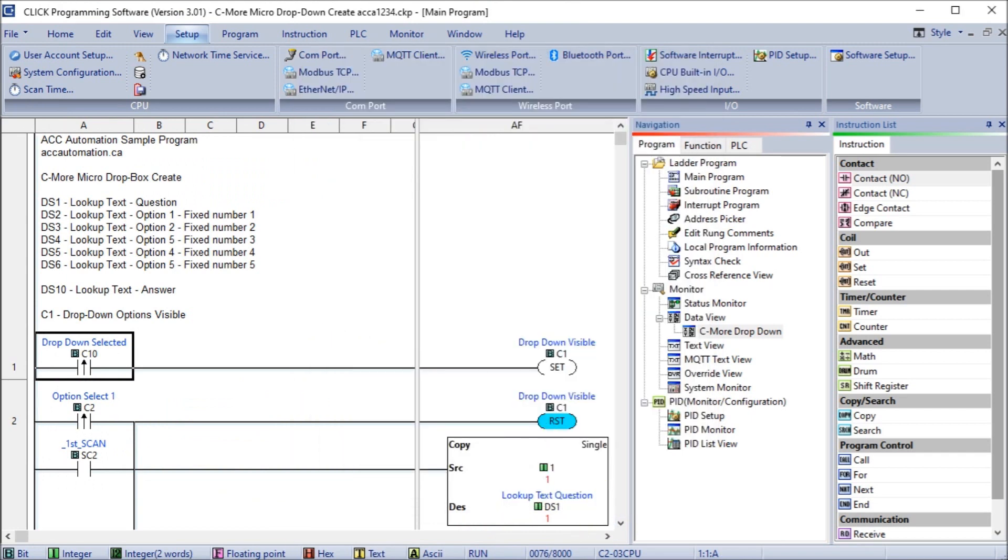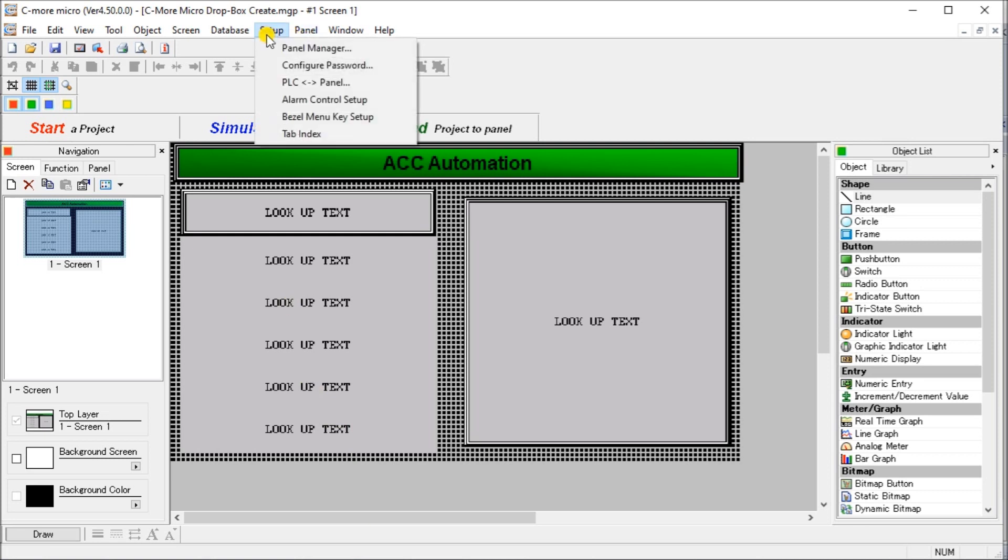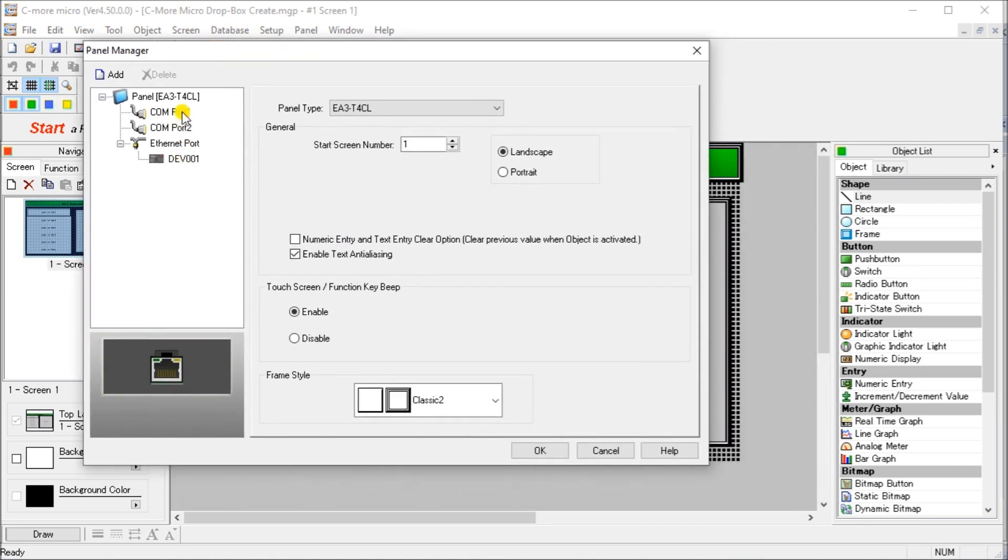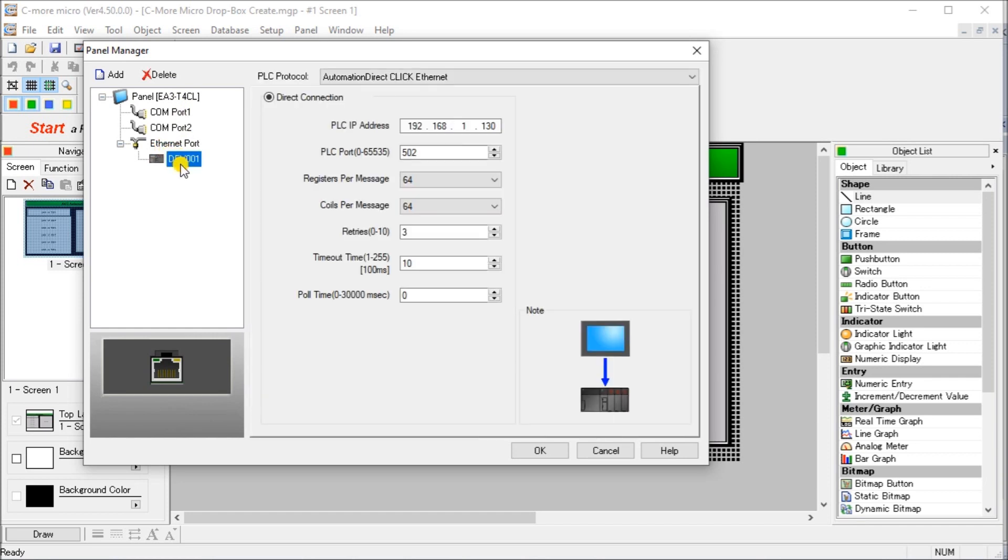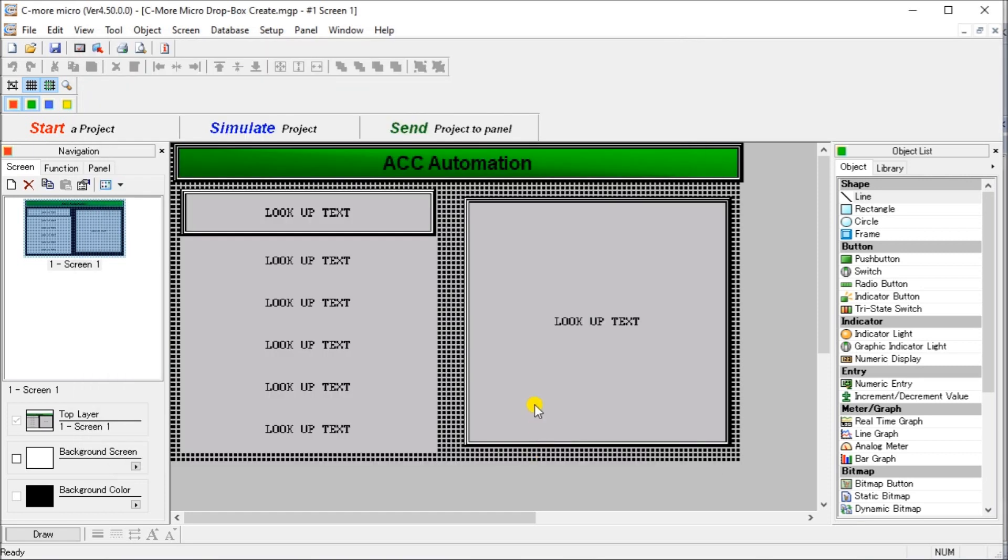So once we have our port set up, now let's go back to our C-more micro programming software and we can go to setup. And then under panel manager, you will see that we have our panel, which is an EA3 T4CL, which is the micro C-more line. And our communications is under the Ethernet port. It's the DEV001. You can see that we have our automation direct Click Ethernet protocol selected. And we have selected 192.168.1.130, which is pointing to our Click plus Wi-Fi network.